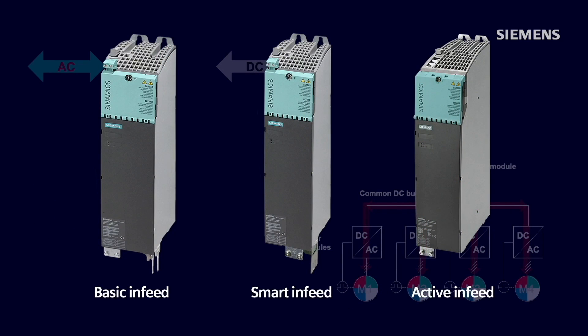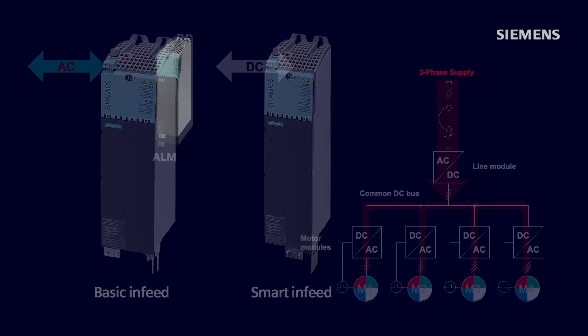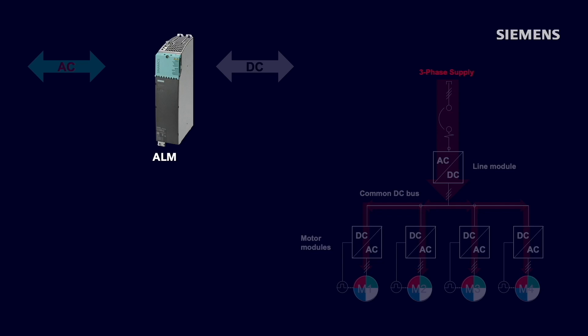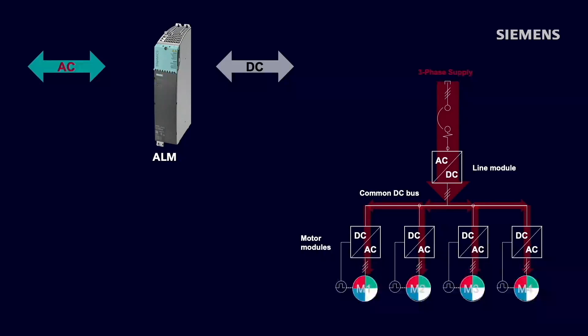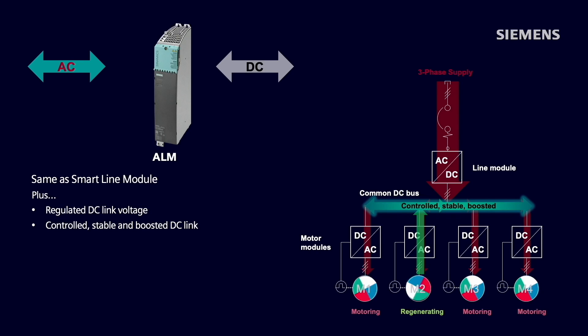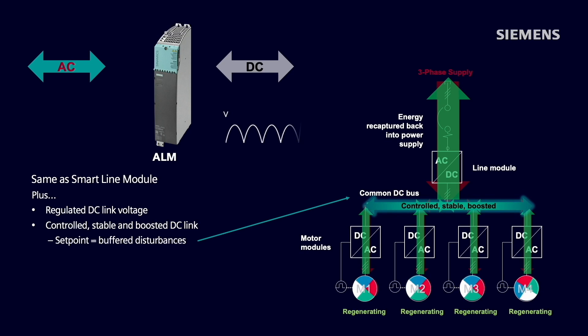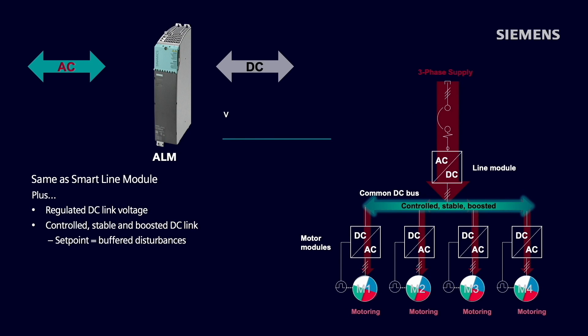Focusing next on using an active line module, which offers the highest performance in addition to being fully regenerative, this option also controls the DC link voltage, so it remains stable and without ripple. If we have any disturbances, whether it be on the incoming power supply or effects from the motor, the disturbances would be buffered out because we're controlling that DC link as a set point value.